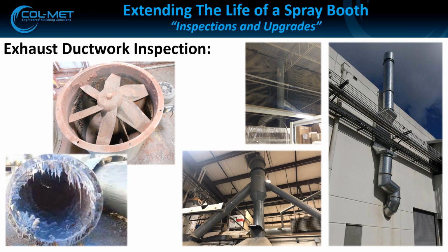That's important to a fan because as the duct diameter changes in size, let's say we've got an inch of buildup. We've lost 1 inch of diameter all the way around that pipe, a 1 inch annulus of duct, so you can say we've lost 2 inches in diameter. That increases our speed through the ductwork, which increases static pressure. That gives our fan less ability to move the CFM it was designed for, and less time to do filter load. When you run multiple ducts into a single piece of duct, this happens out in the field all the time. Guys just want to have one penetration, but you have to figure for those things.